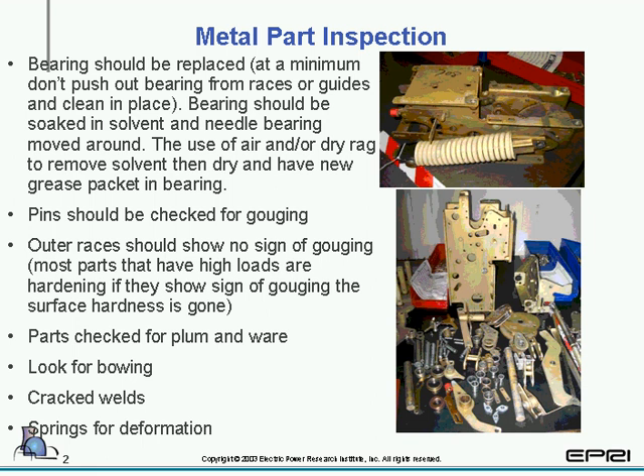Metal part inspections. Along with our list, when you disassemble the breaker, you want to inspect the parts for any type of wear. As a rule of thumb, on your pins, if you run your fingernail down it, and your fingernail will lodge into the piece or get stuck, it's normally rejected. Most parts on most design breakers are hardened to some degree, or surface or case hardened to some degree. If you lose that surface hardening, the pins will wear out.